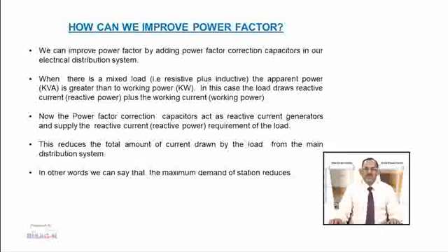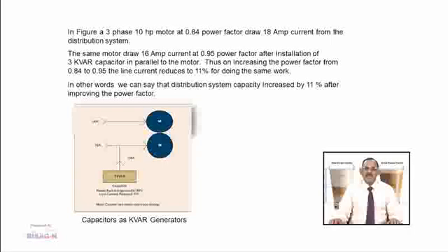In this case, the load draws reactive current (reactive power) plus working current (working power). Power factor correction capacitors act as reactive current generators, supplying the reactive power requirement of the load, which reduces the total current drawn from the main distribution system. For example, a 3-phase 10 HP motor at 0.84 power factor draws 18 amperes, but after installing a 3 kVAR capacitor in parallel, the same motor draws only 16 amperes at 0.95 power factor — a reduction of 11%.